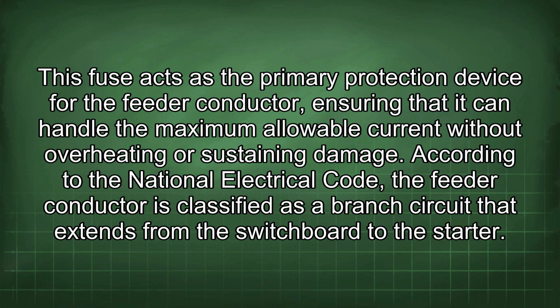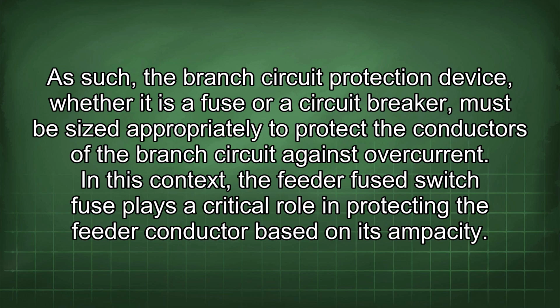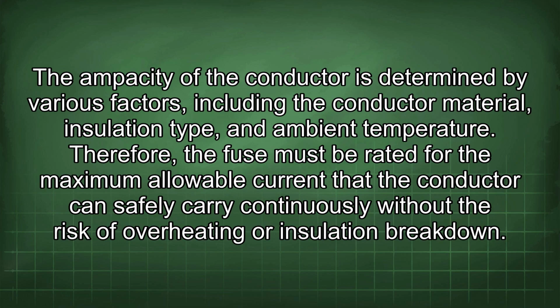According to the National Electrical Code, the feeder conductor is classified as a branch circuit that extends from the switchboard to the starter. As such, the branch circuit protection device, whether it is a fuse or a circuit breaker, must be sized appropriately to protect the conductors of the branch circuit against overcurrent. In this context, the feeder fused switch fuse plays a critical role in protecting the feeder conductor based on its ampacity. The ampacity of the conductor is determined by various factors, including the conductor material, insulation type, and ambient temperature. Therefore, the fuse must be rated for the maximum allowable current that the conductor can safely carry continuously without the risk of overheating or insulation breakdown.